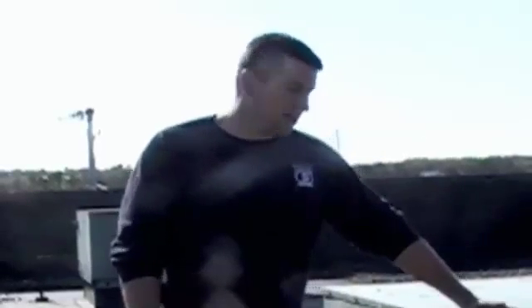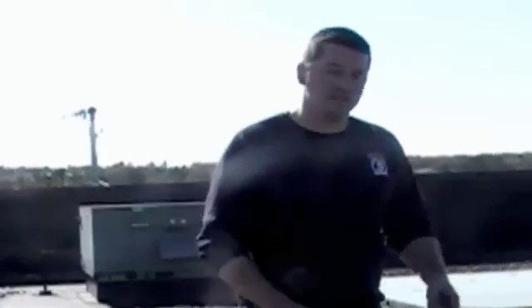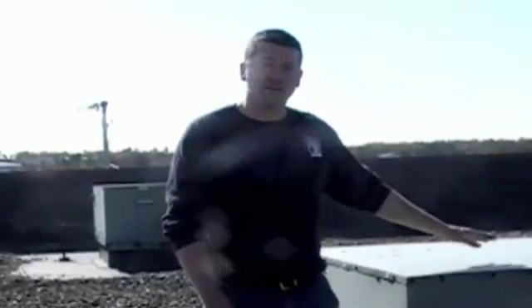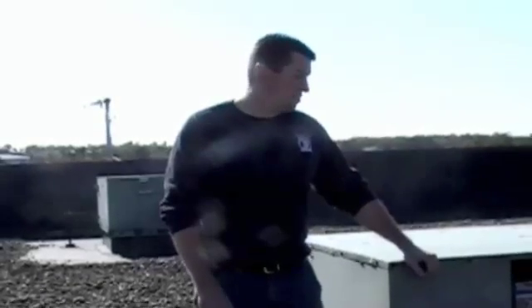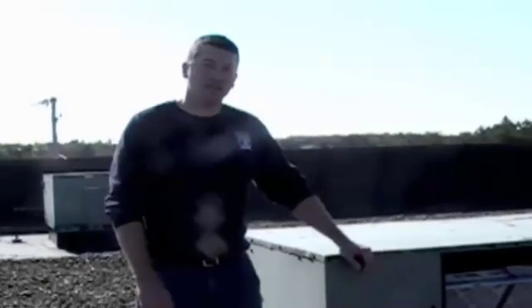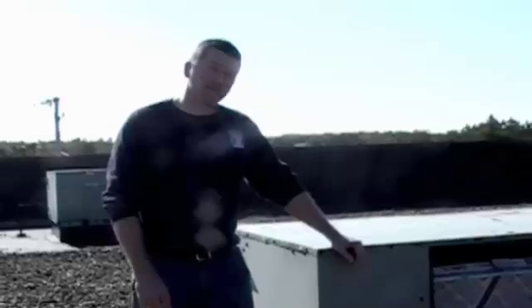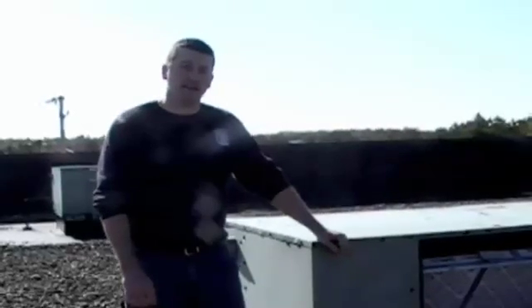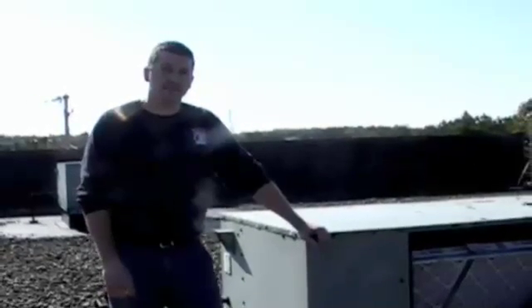So to recap what we've done today, we set up our two loggers to measure supply temperature, compressor amperage, return air temperature, and relative humidity of the space. Both of our loggers are set up, mounted in the unit. The interval is going to be 1 minute reads, and we're going to measure these for 10 days and then come back and analyze the data. Thanks.